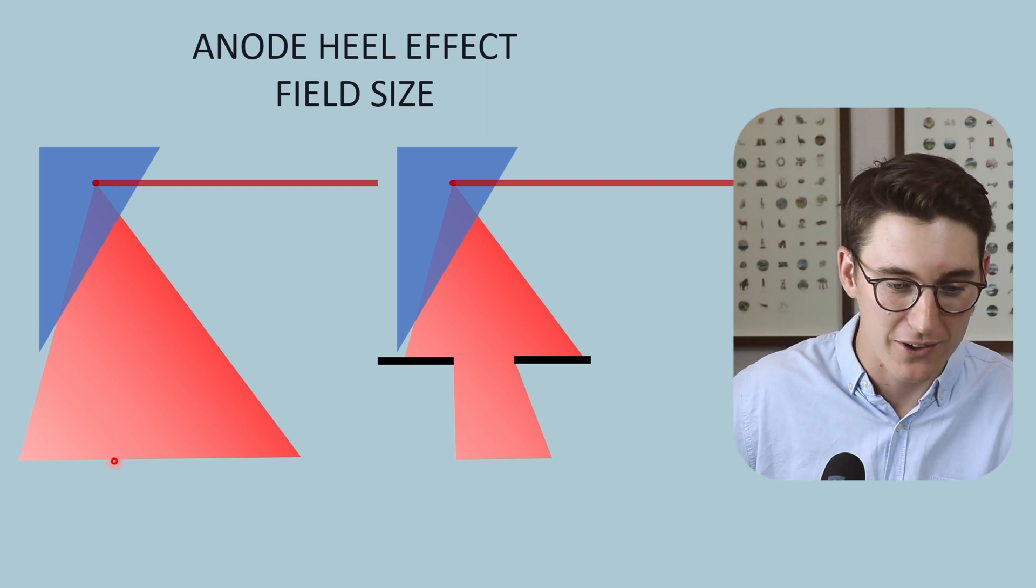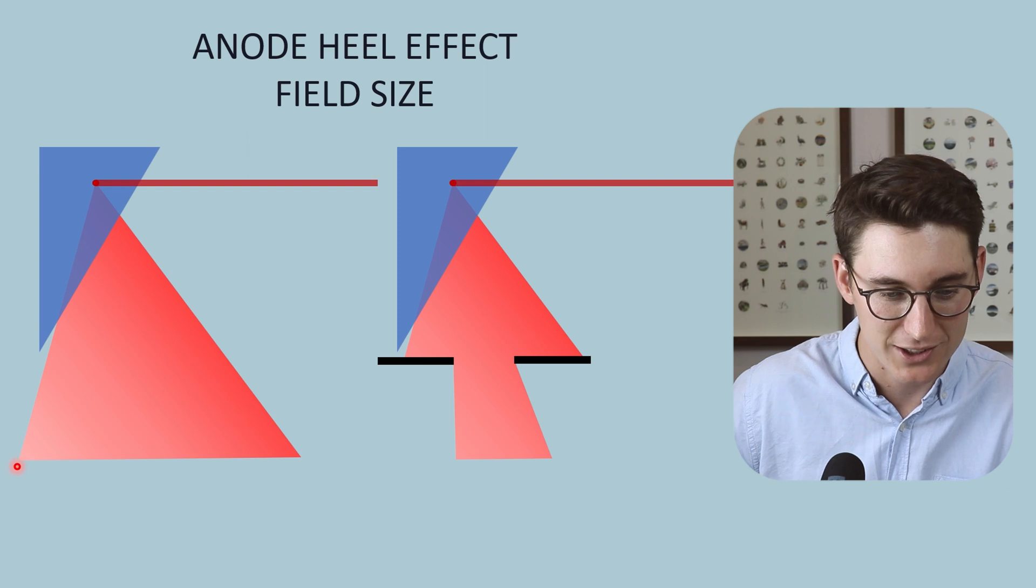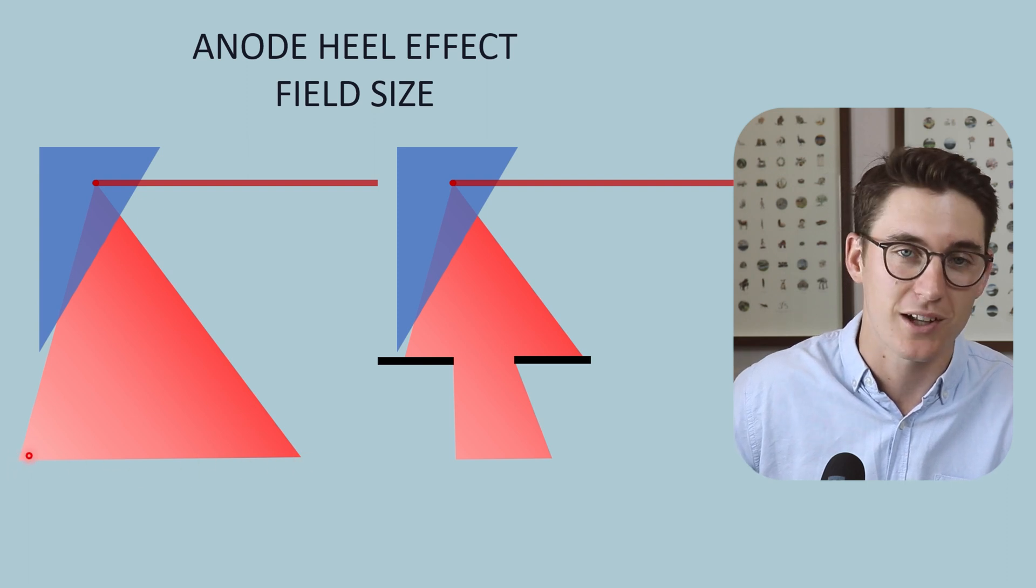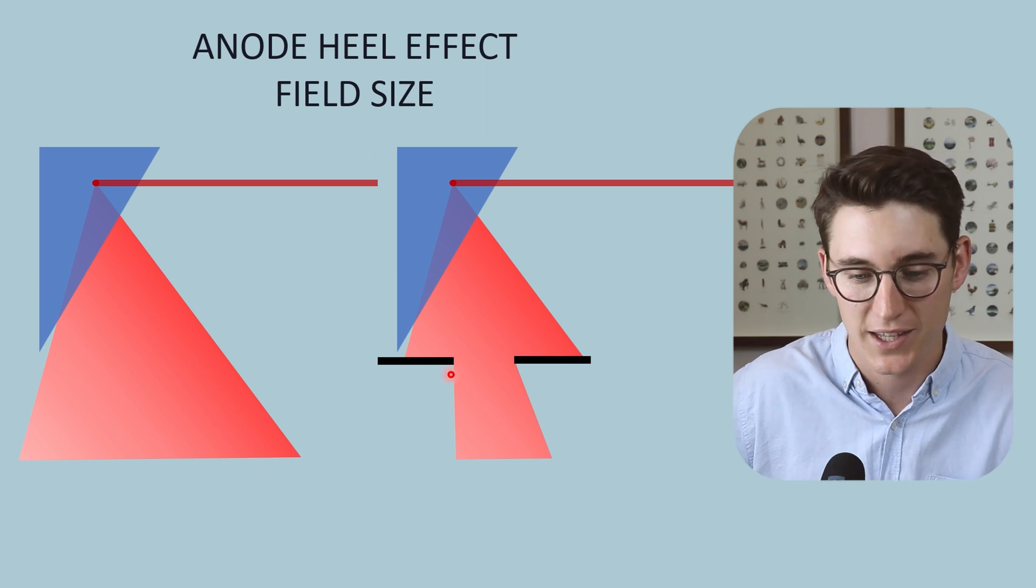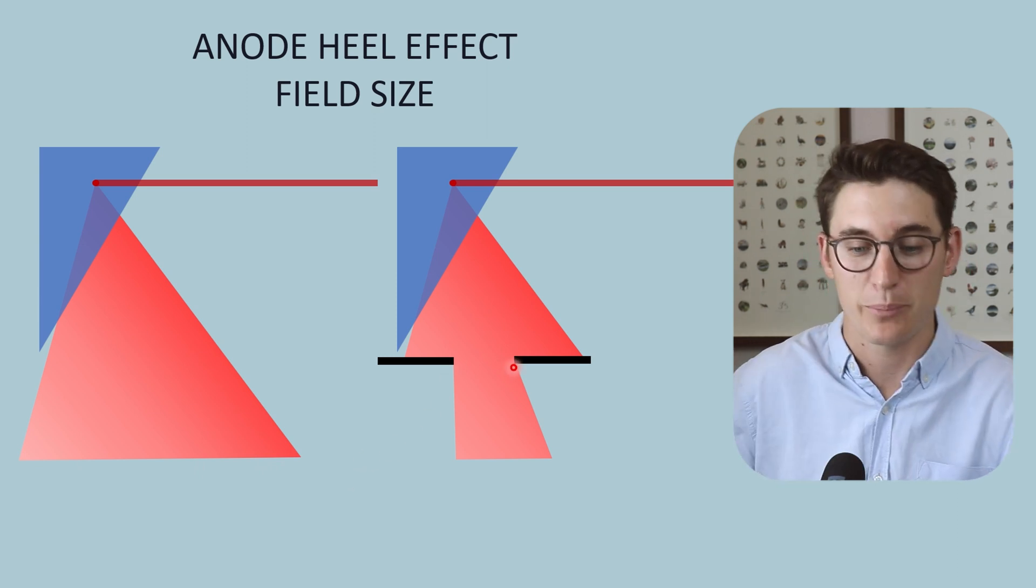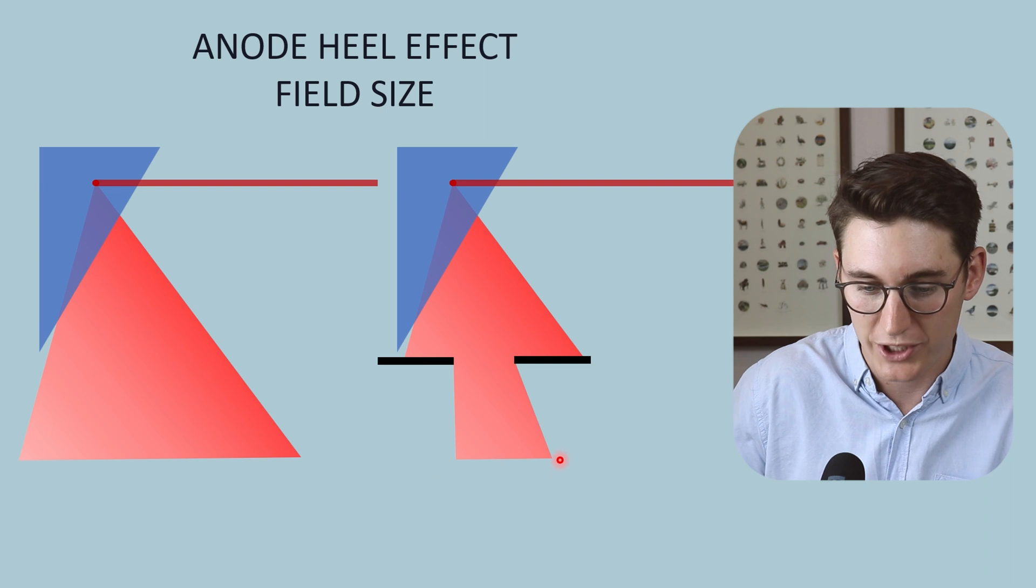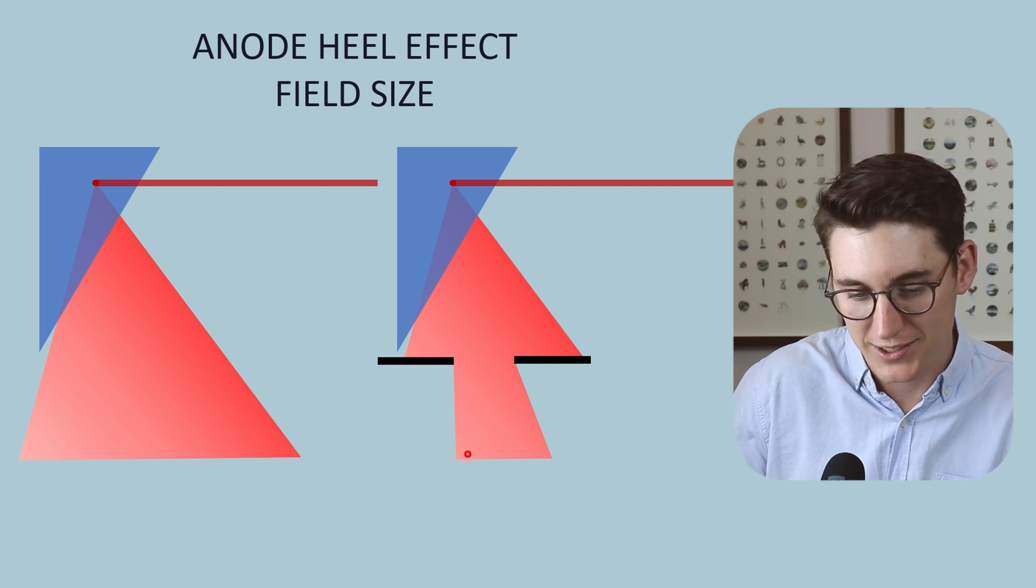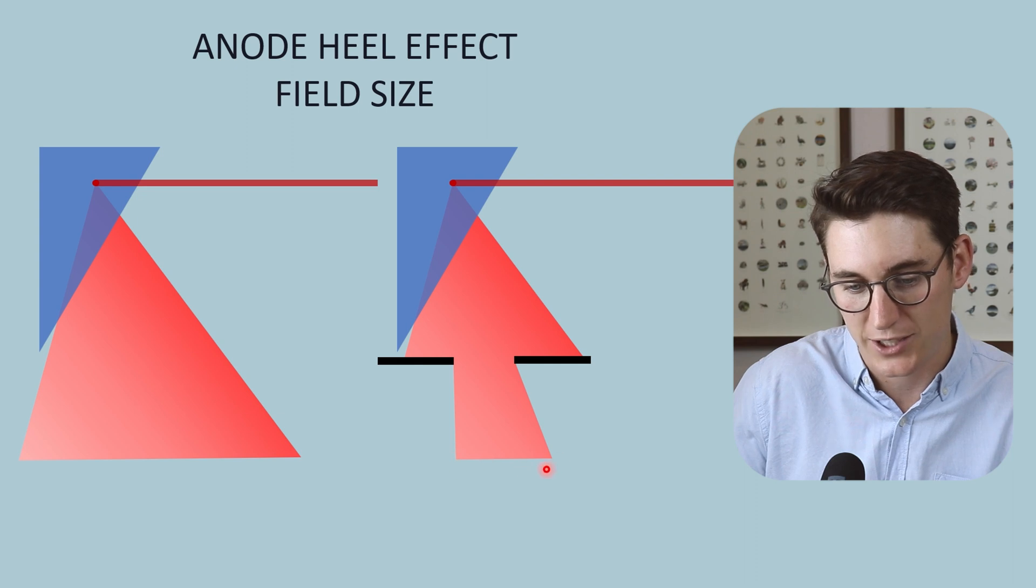If we use our entire field here to create our image, our detector will experience the entire range of intensities between our anode and cathode sides. If we collimate that beam down to a small region, that differential in intensity is much less if our detector was now detecting all of these x-ray beams.